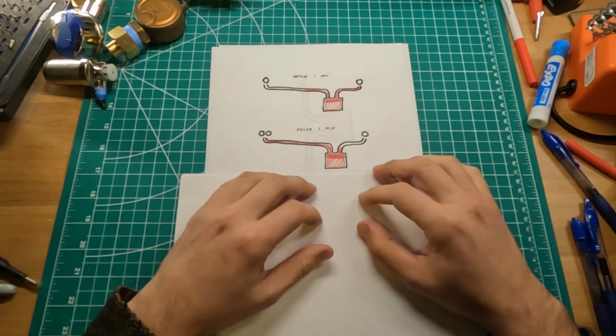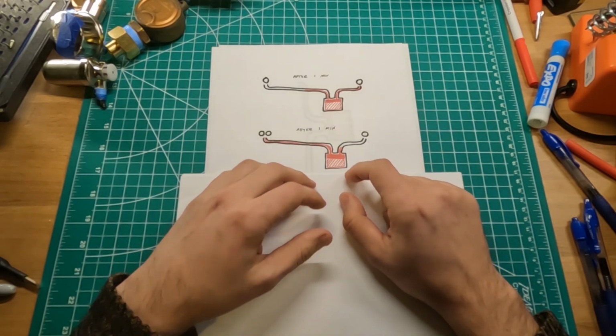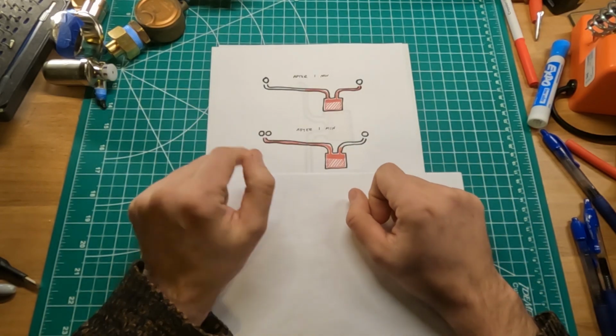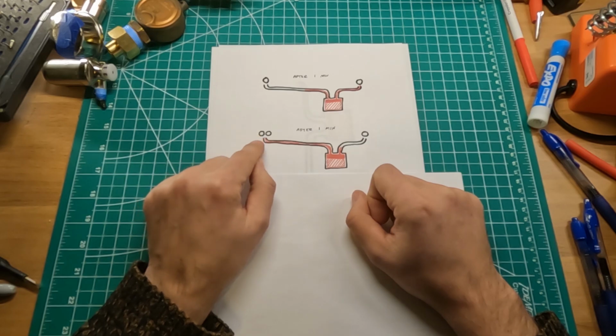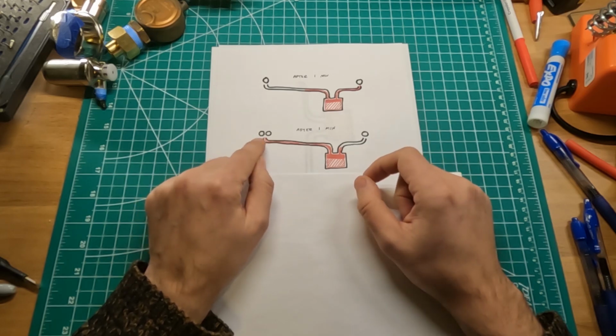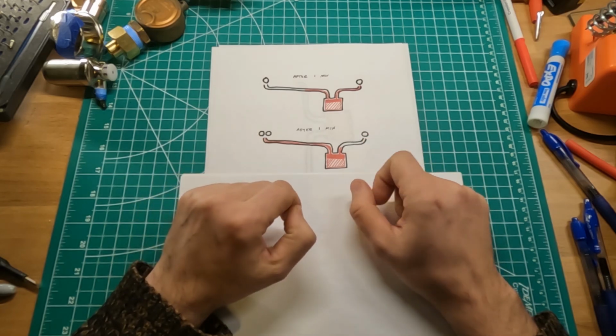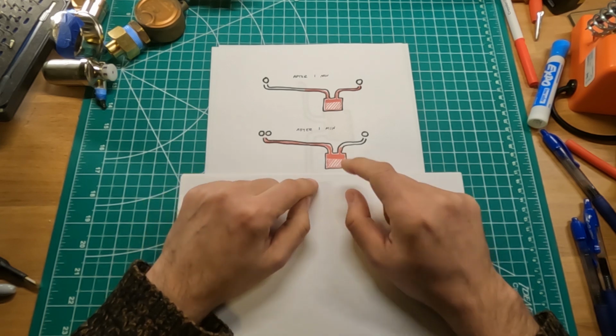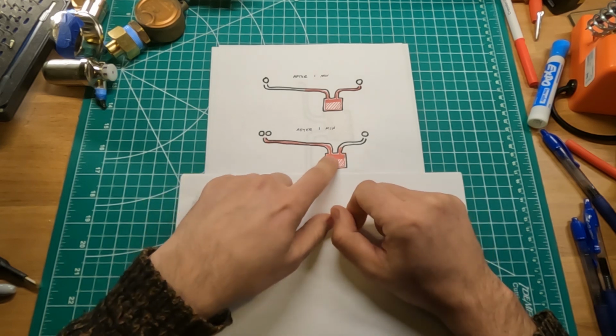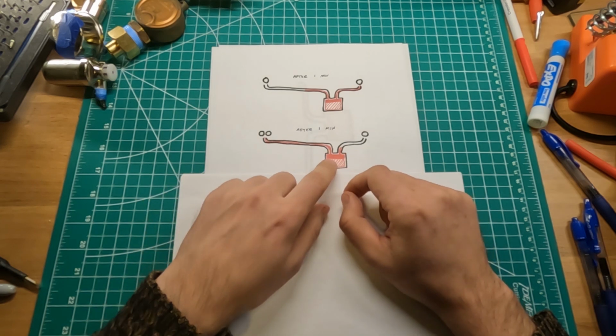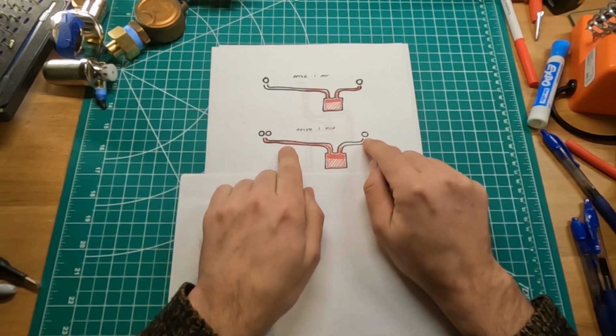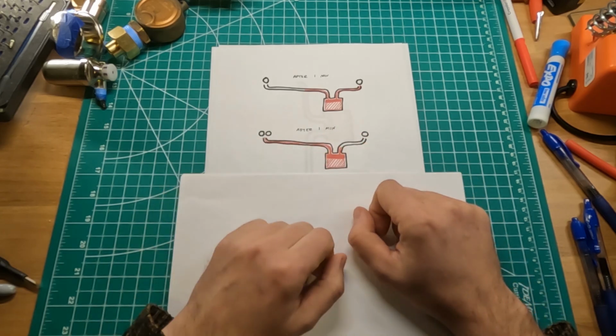Once again, similar scenario. We have a boiler, two main pipes, but something interesting happens. When you added two vents to this side, which means basically double the venting rate of this side, if you notice, pretty much all the steam at the beginning of the steam cycle, instead of equally spreading to both of those vents, went in this direction.